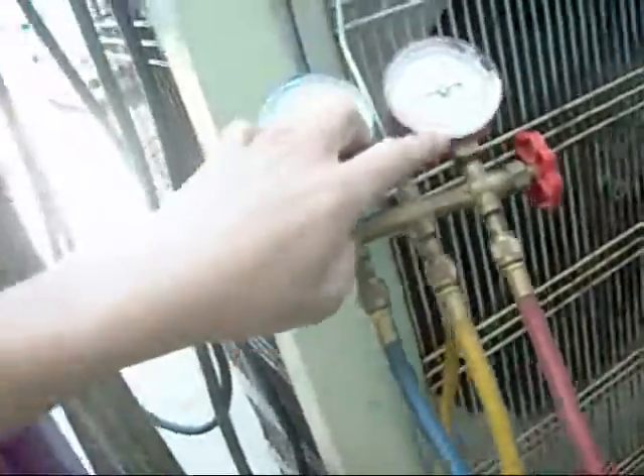This one here is running for about 5 seconds and then shutting down. High pressure is going up to 450lbs and then it kicks out. So it seems a bit high to me, and there's a funny little thing going on.